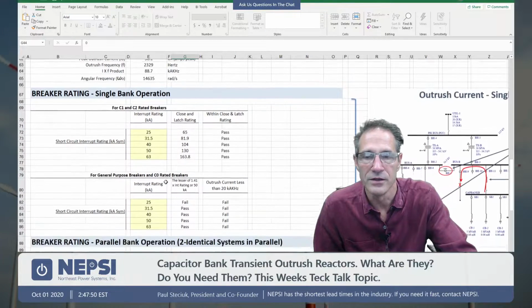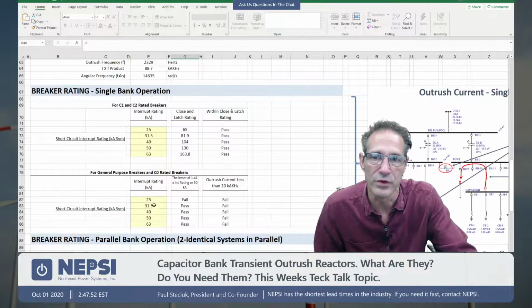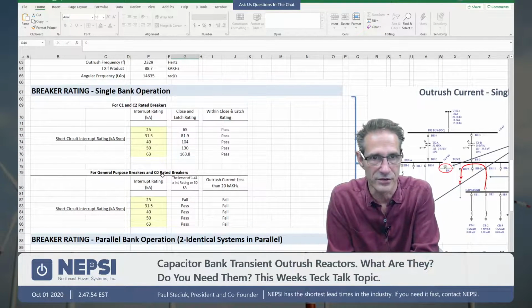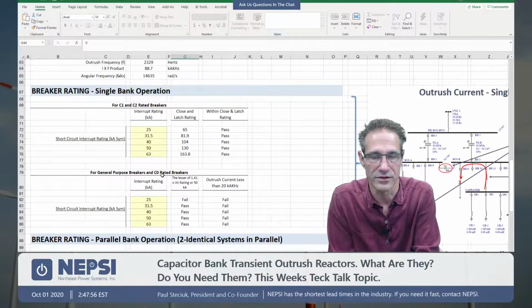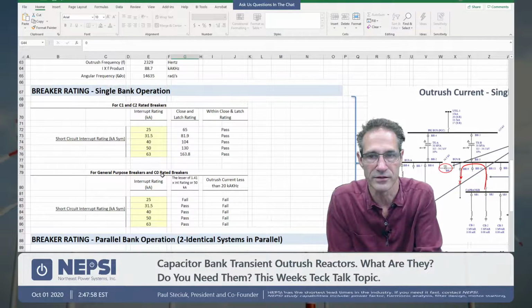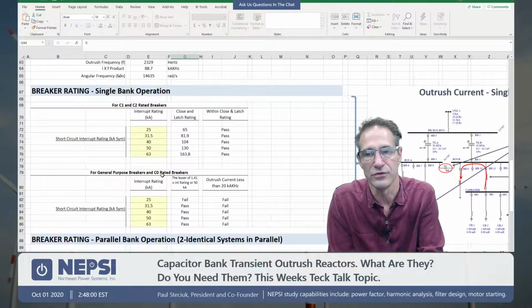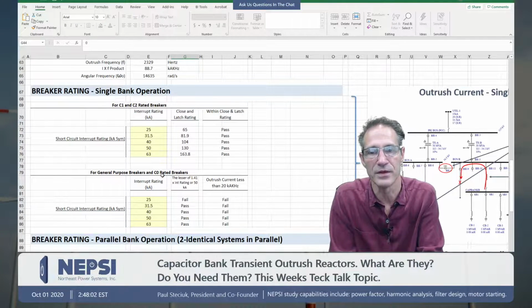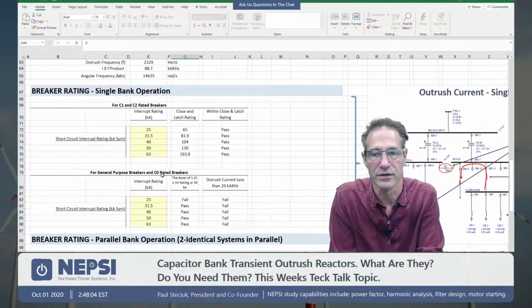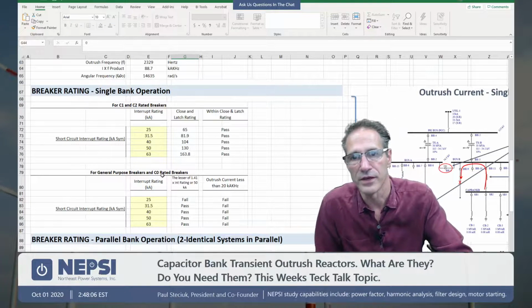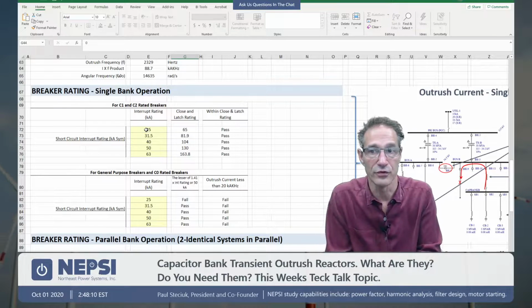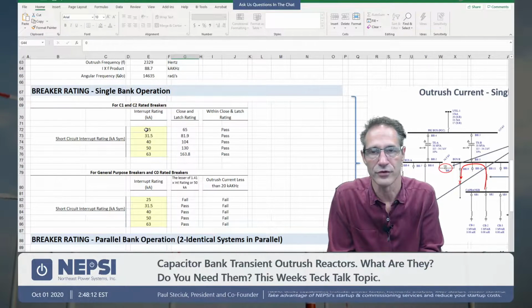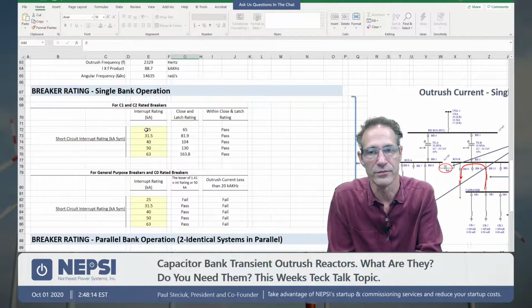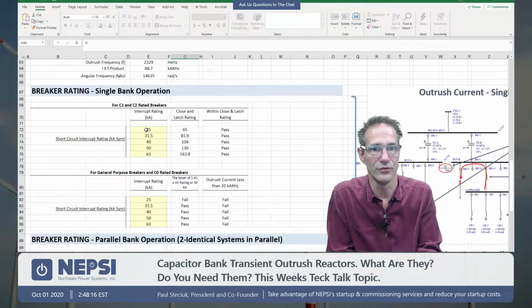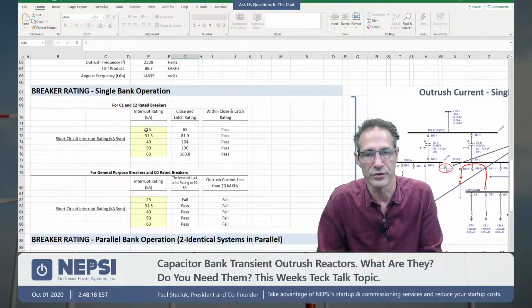And depending upon what type of breaker you're dealing with, if it's a C0 breaker, meaning it's not really designed for capacitor switching, there is a possibility of restrike. You have a set of parameters that you're evaluating for that breaker, and then you have C1 and C2 rated breakers, which are those that have a lower probability of restrike. Remember, C1 is low probability of restrike, C2 is very low probability of restrike.